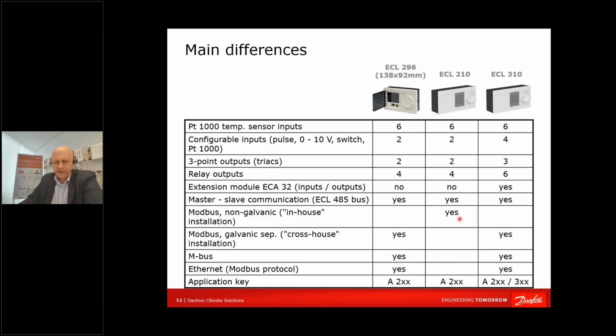Modbus, not galvanically separated, in-house. Yes, only ECL 210 has it. Modbus galvanically separated for the BMS: these 2 have it. M-bus, you can connect meters to ECLs. We'll speak about it later on. Ethernet, you can connect ECL to the cloud. Application keys, as you can see: ECL 210 can work only with the keys which start with a letter or digit 2. ECL 310 can accommodate both of them.